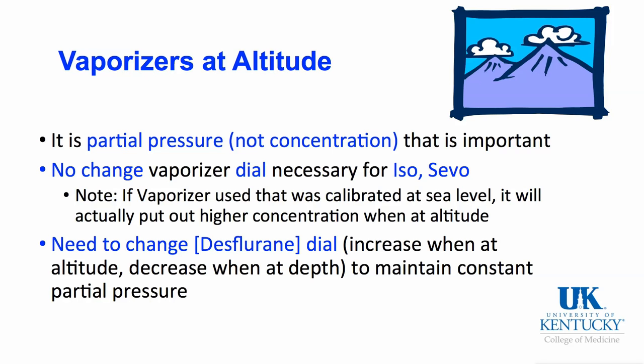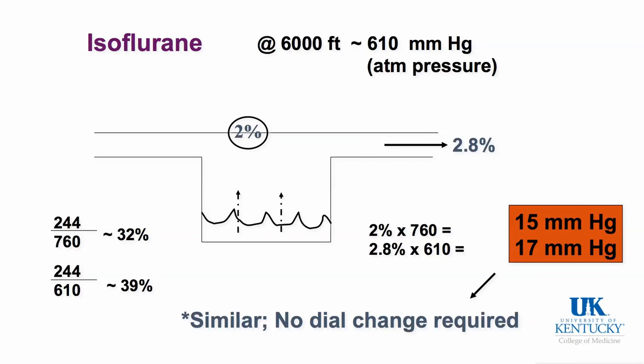However, desflurane in its own little environment does need to be altered. The dial actually would have to be increased, turned up, higher concentration if you took the desflurane vaporizer up to altitude. So let's look at this as an example.